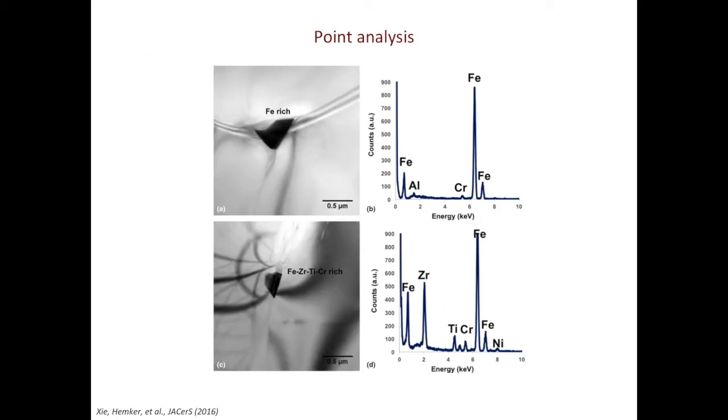When acquiring EDS data, you can do point analysis, line scan, and EDS mapping. Point EDS is pretty straightforward. You just dwell your beam on feature of interest, then collect the EDS data. In the examples shown here, EDS spectra were acquired from these precipitates. The precipitate on the top is rich in iron with small amount of aluminum and chromium. The precipitate down the bottom is rich in iron and zirconium. There's also small amount of titanium, chromium, and nickel.